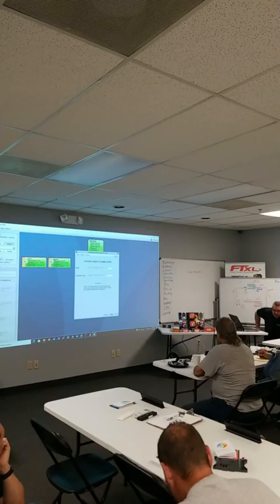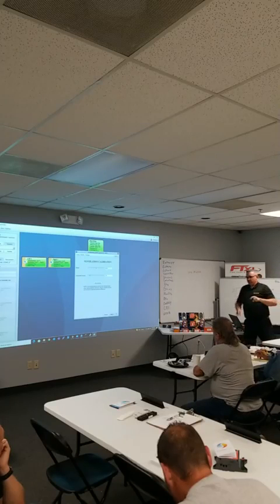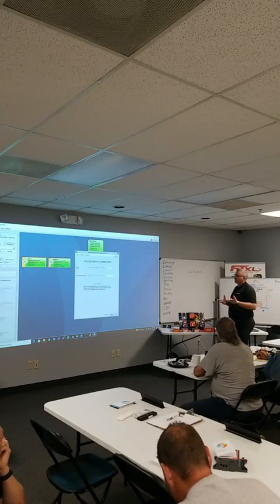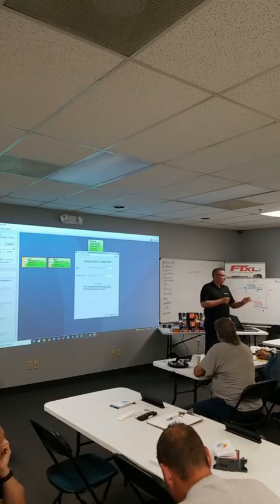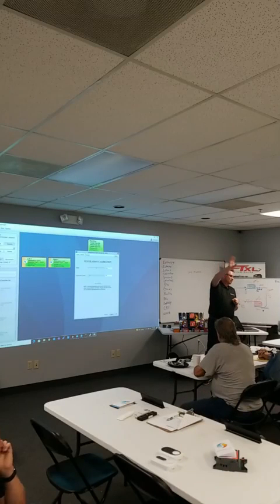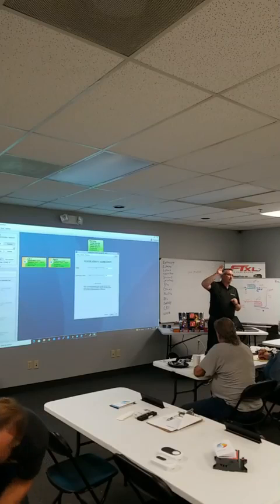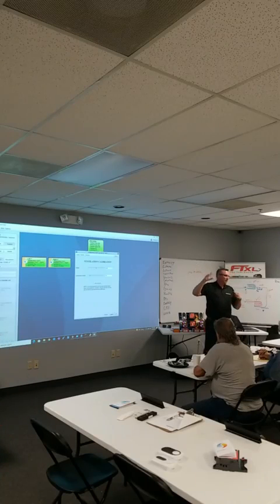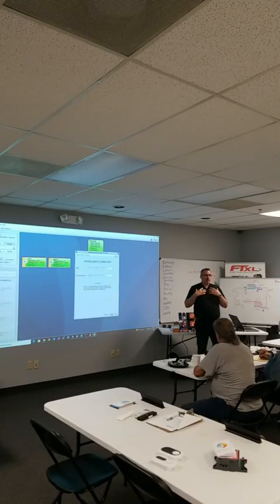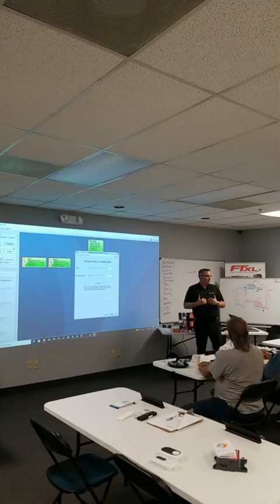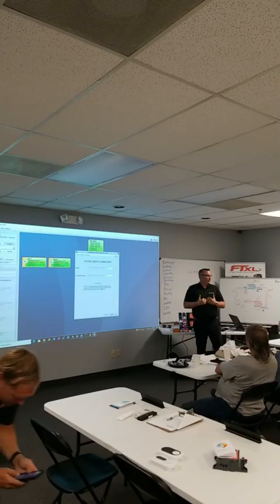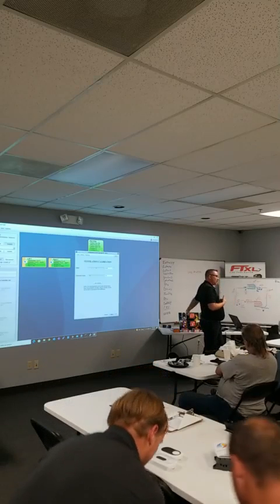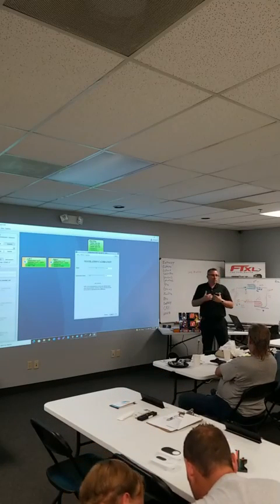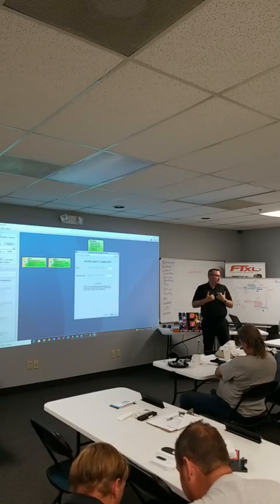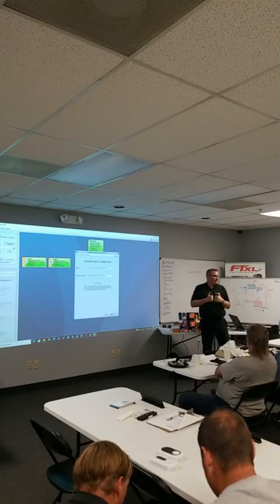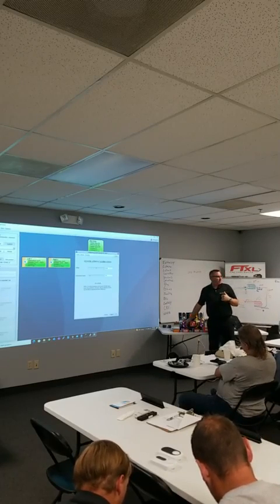So, how many of you have done VAVs before? Alright. They use the words test and balance, it drives me nuts. It's calibrate, and then they need to go manually balance all of the manual dampers to each diffuser. So a lot of times the portion that the control guy is involved with is the calibration. Because what we're trying to do is verify that the VAV box is reading what the balancer read at each of the diffusers. So the balancer is going to go read all the diffusers, give you a number, and we need to calibrate to make sure that that's that.